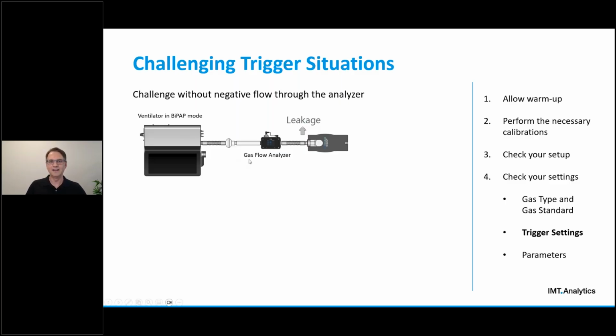In this example, we have a ventilator in BiPAP mode that applies pressure on two different levels to a test lung. And the test setup is equipped with a defined leakage in front of the test lung to simulate a typical patient interface with a non-invasive ventilation interface, for example, a mask with a leak. In this application, there is no negative flow through the gas flow analyzer during the exhalation phase, because all the volume that comes out of the test lung is going to leave through this leakage. And therefore, the flow in the flow channel of our analyzer never goes negative. And that means that our previously discussed default trigger settings are no longer going to work.